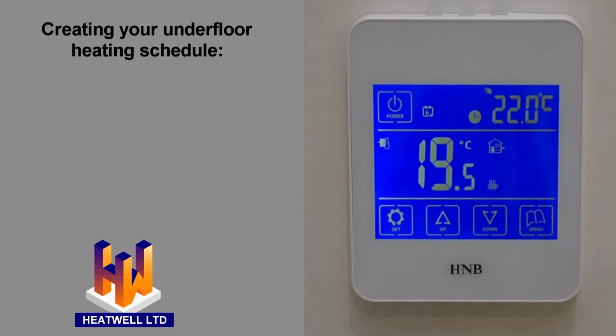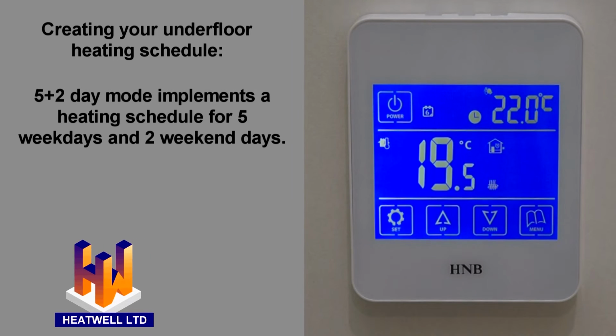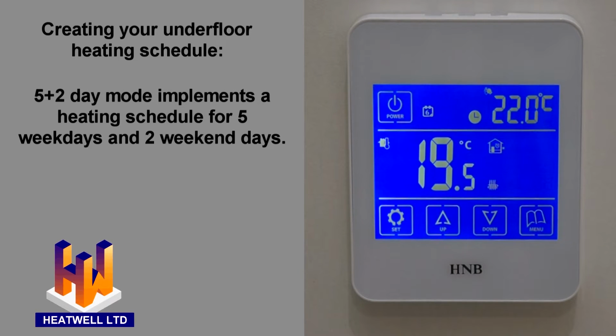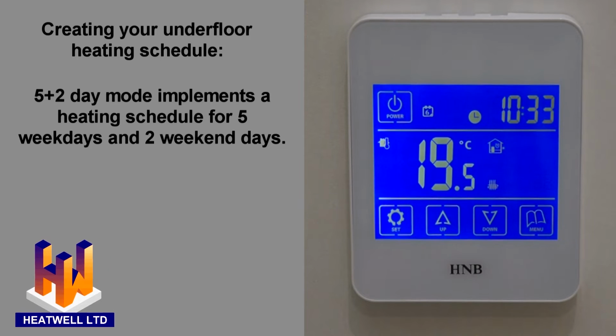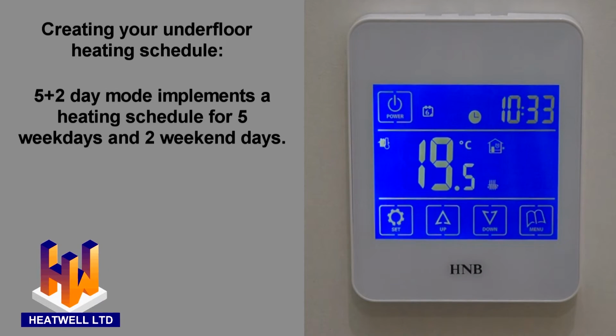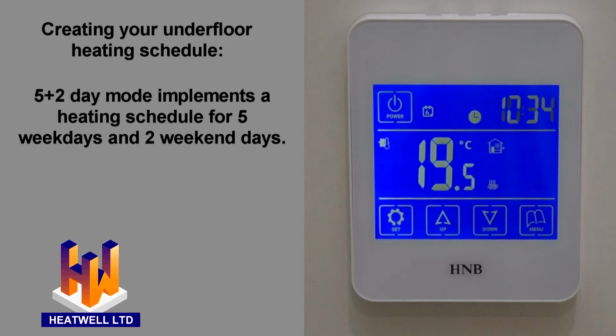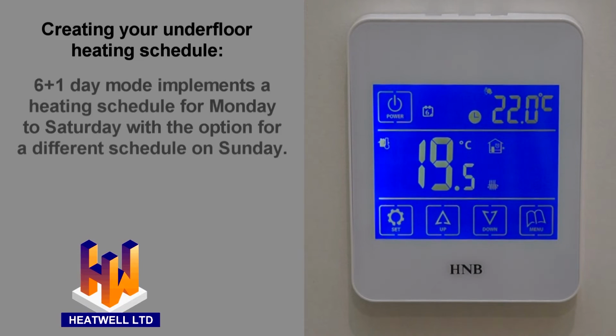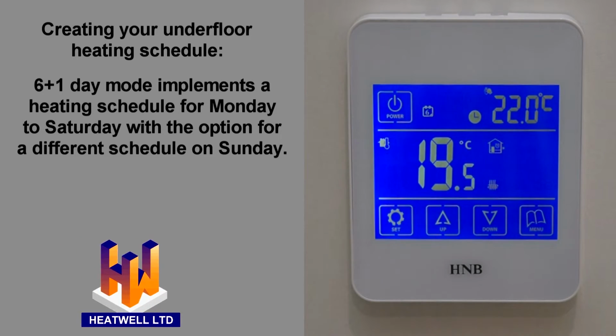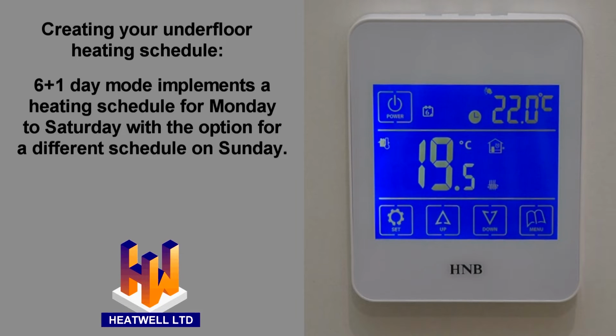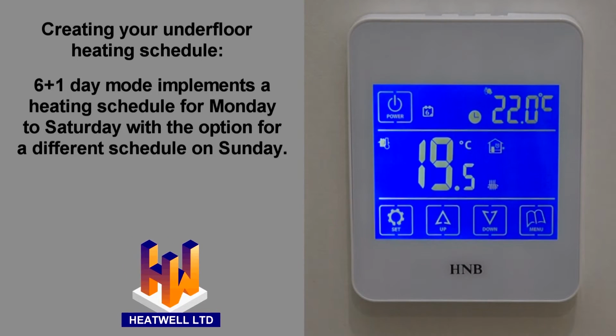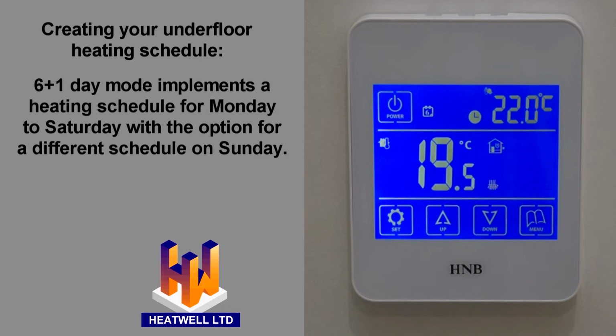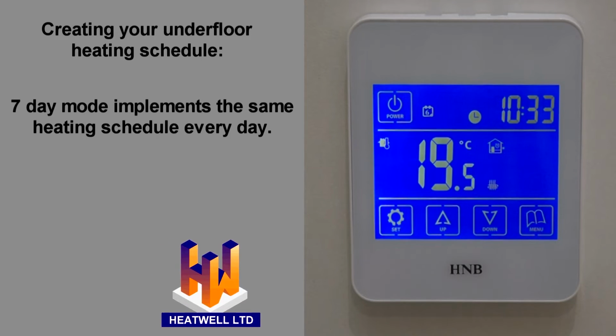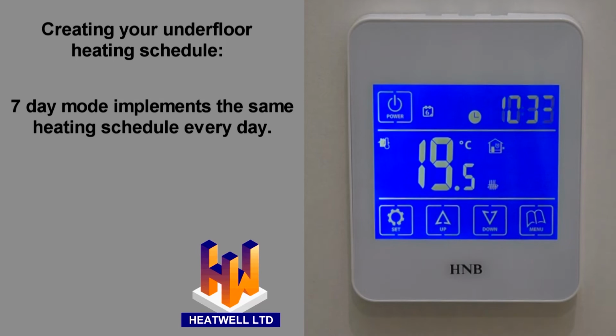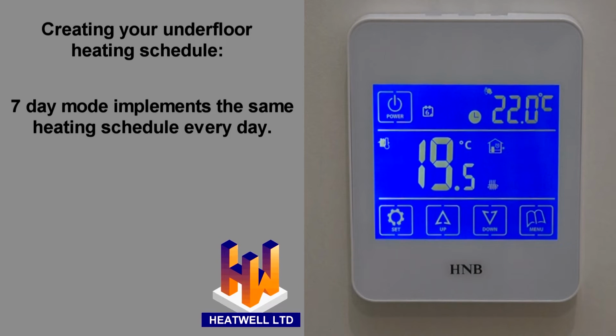Creating your underfloor heating schedule. The thermostat has 3 schedule options. The default setting is 5+2 day mode, allowing you to set floor activation times and temperatures for 5 weekdays plus 2 weekend days. There is also the option for 6+1 day mode, covering Monday to Saturday with different activation times and temperatures for Sunday. And lastly, there's 7-day mode, which applies the same floor activation times and temperatures every day.